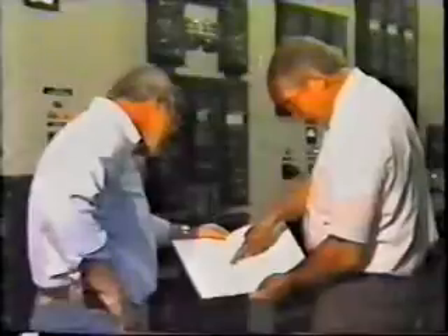Before any equipment can be energized, it is essential that the related protective schemes be tested and placed in service, even though further adjustment may be required later. This videotape focuses on the commissioning tests related to protective schemes, even though reference may be made from time to time to primary equipment. Most power companies have their own set of commissioning procedures. Make sure you have access to these documents.